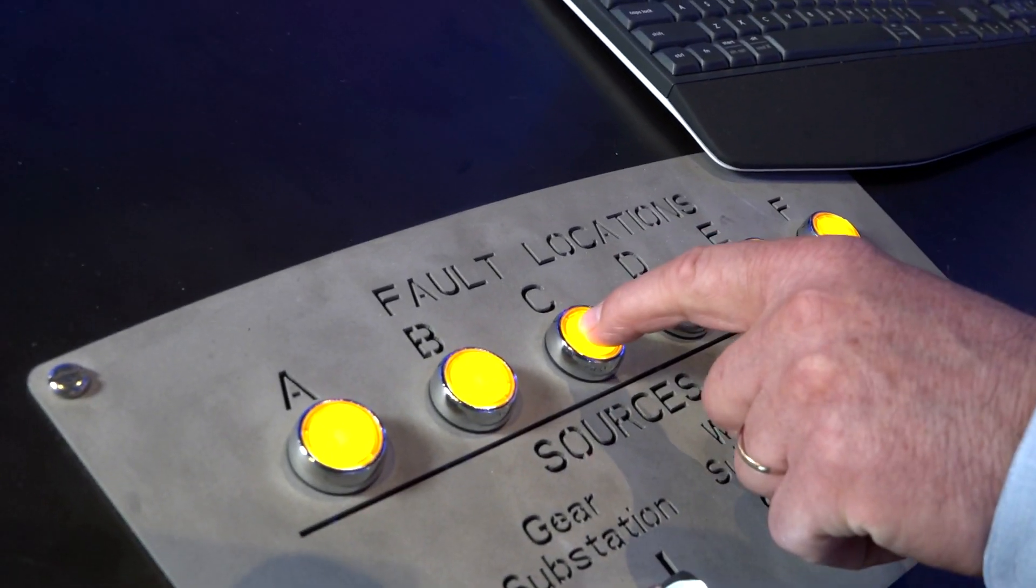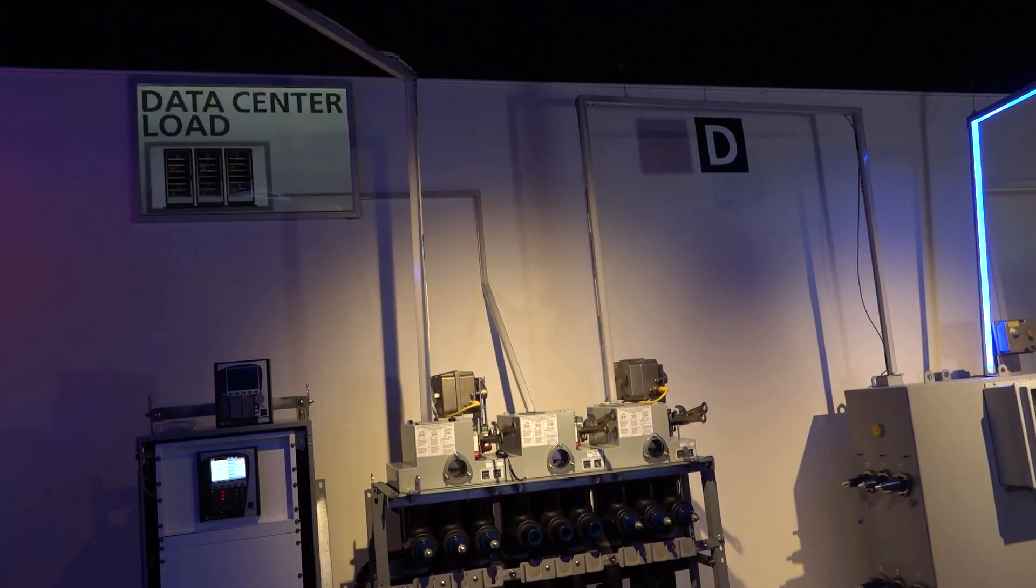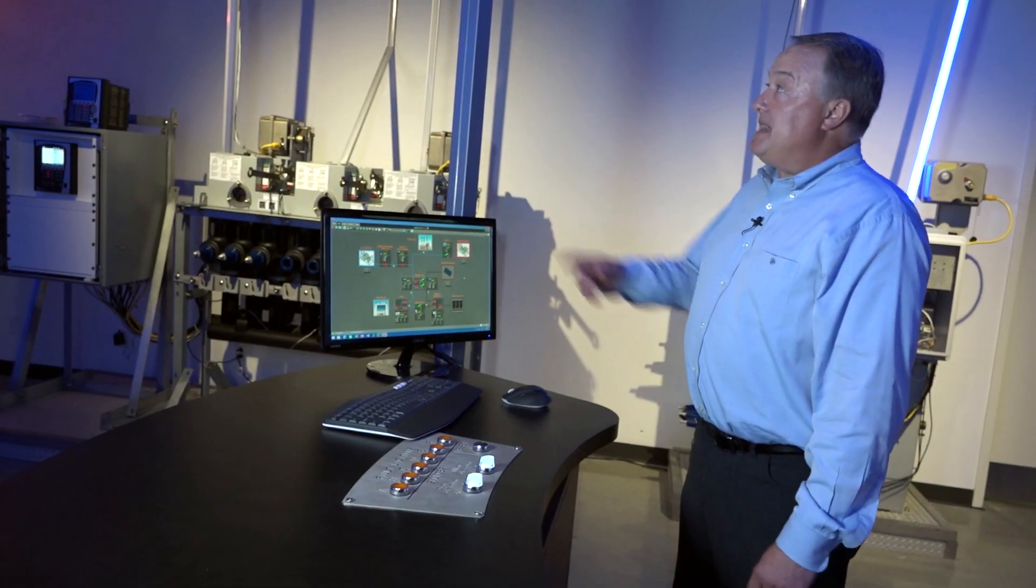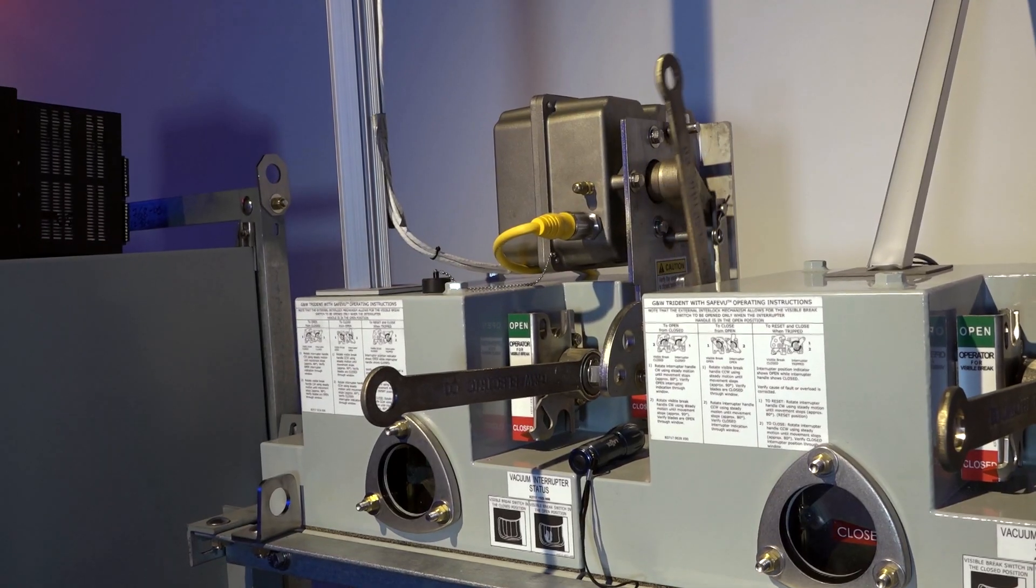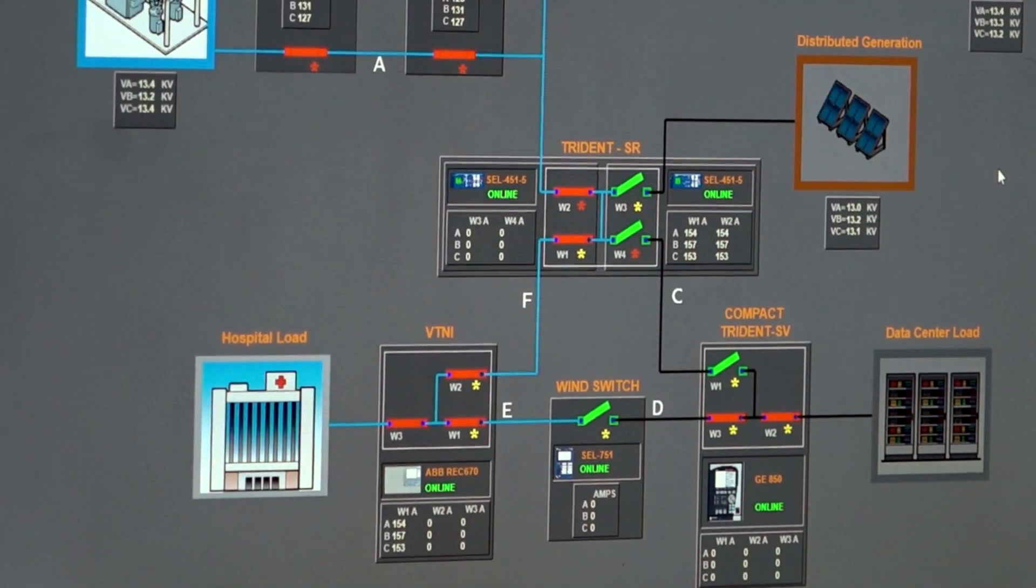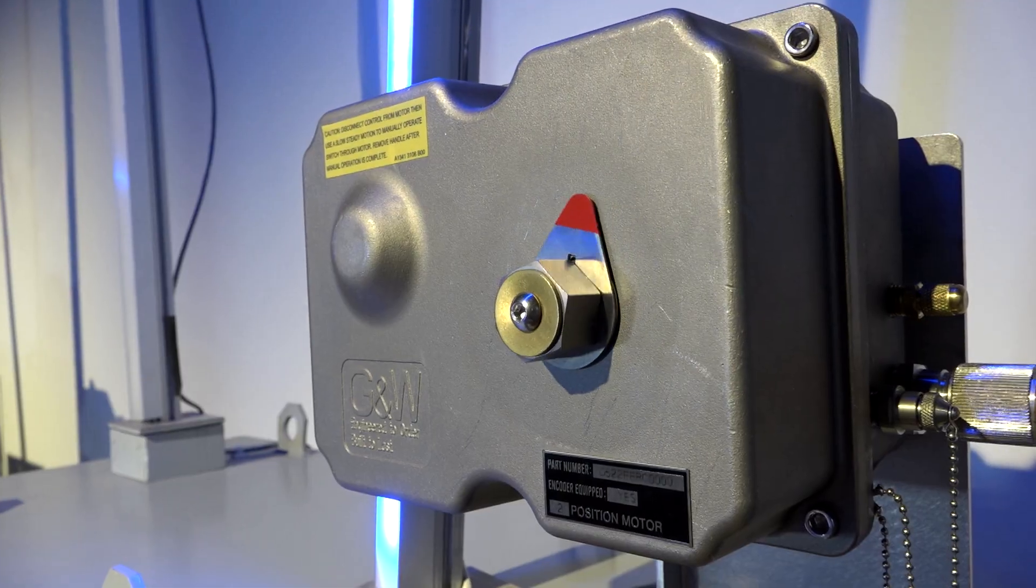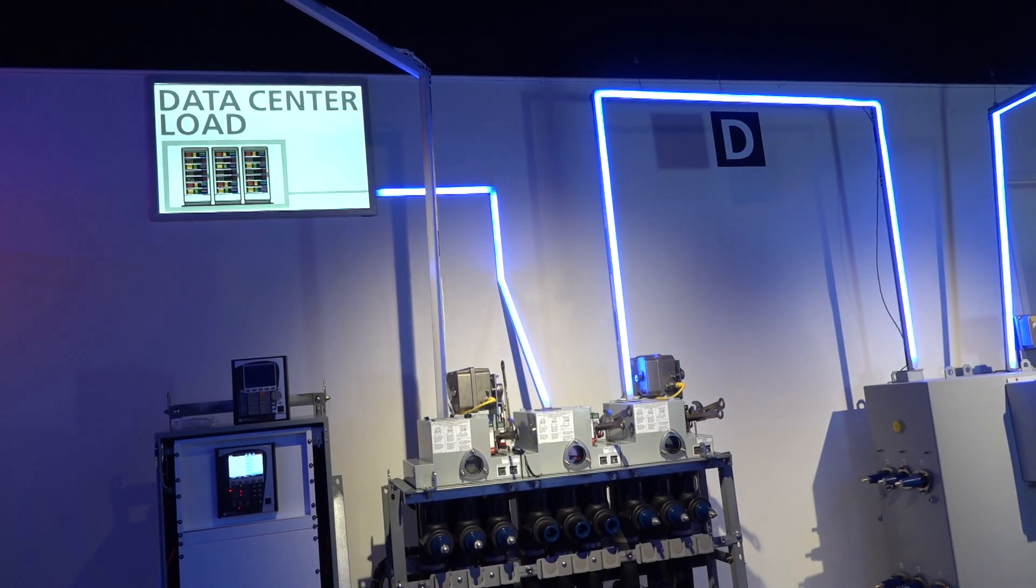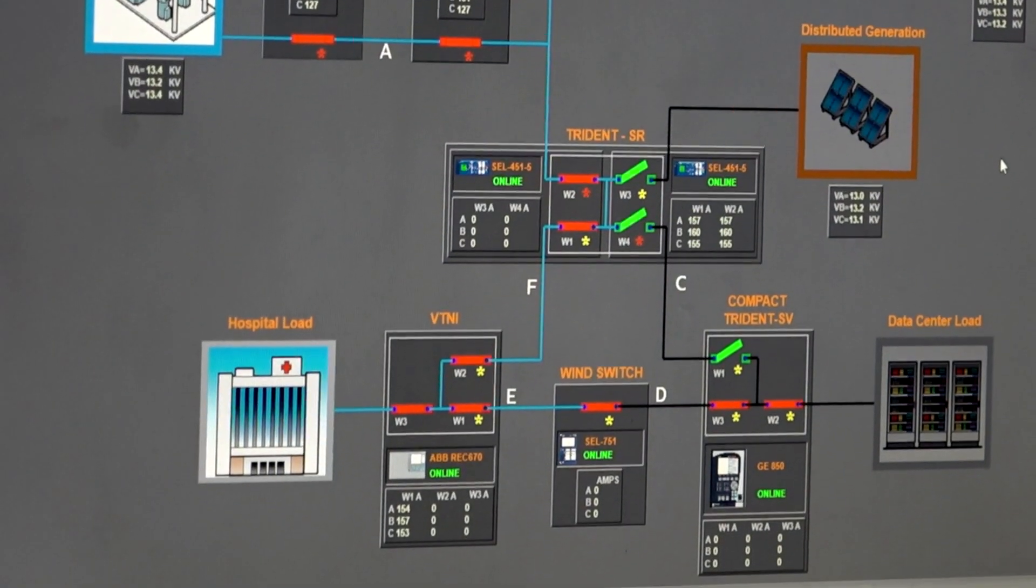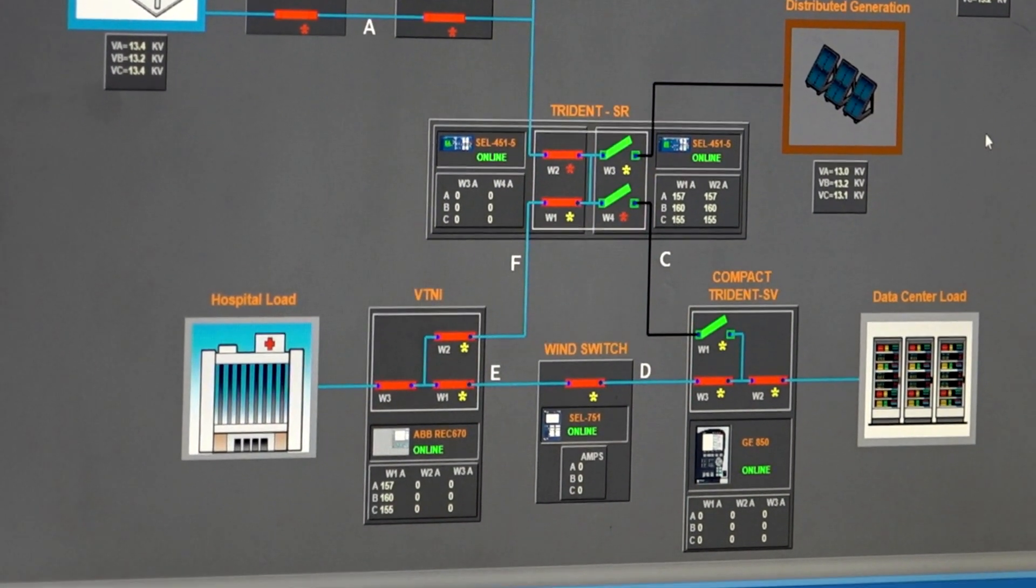So I'm down C and D sections. I'm going to open on each side of the fault. And then I'm going to close in another source, and I restore D, which happens to be the data center load.